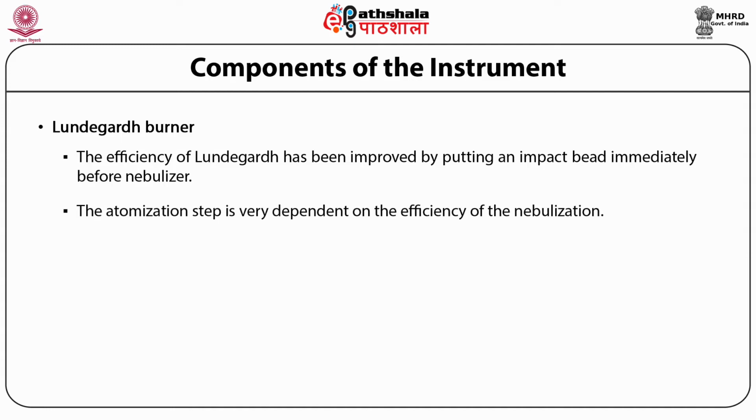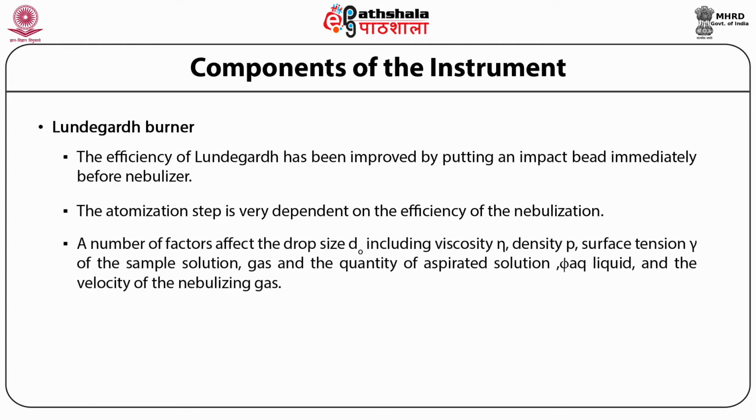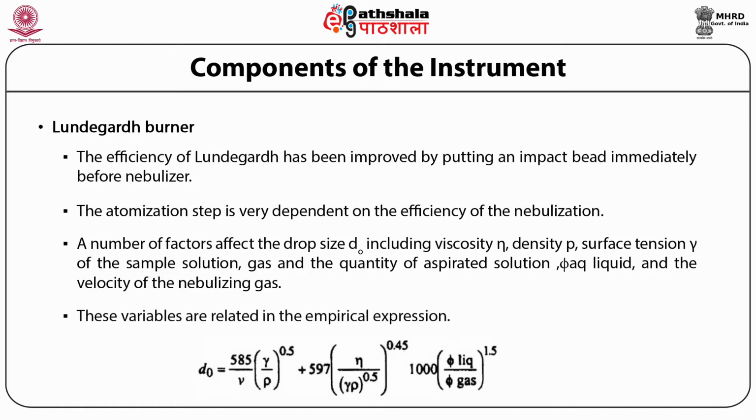The atomization step is very dependent on the efficiency of the nebulization, since the droplet must be evaporated and the residue broken down to liberate free atoms after introduction into the flame. A number of factors affect the drop size, d naught, including the viscosity eta, density rho, and surface tension gamma of the sample solution, the quantity of aspirated solution phi, and the velocity of the nebulizing gas. These variables result in the empirical expression shown here.